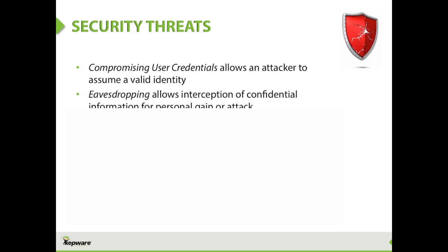If user credentials are just insecure, if they're not using strong passwords, if they get leaked, there's also the case in our space where we're not lazy, right? That's not it, but you install a piece of equipment, it works, and you're a busy guy, you walk away, you got to do something else, right? A lot of times this equipment will have default password settings, and we have a tendency in our space not to change those. So that's just as good as no password at all. Those default passwords are publicly documented. As an attacker, I could get into that system, use a default name and password, and be fully authenticated into the system. So user credentials and having minimum requirements on how difficult those should be are really important. Otherwise, people can get in completely authorized and with all the authority that you don't want them to have.